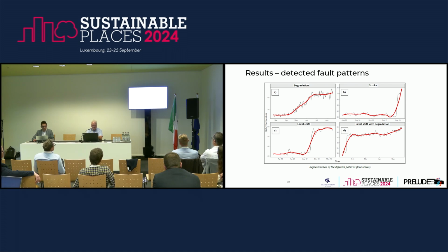Looking generally at many cases, we identified different fault patterns. The one in the top left corner we call degradation, where over several months the system performs worse and worse, having higher and higher return temperature over time. We have another one we call stroke, where suddenly the return temperature increases a lot. Another one we call level shift, where we have one level in a certain period, then a stroke, then another level later on — which we call level shift with degradation. So there are different fault patterns that we can identify when we look into the data.